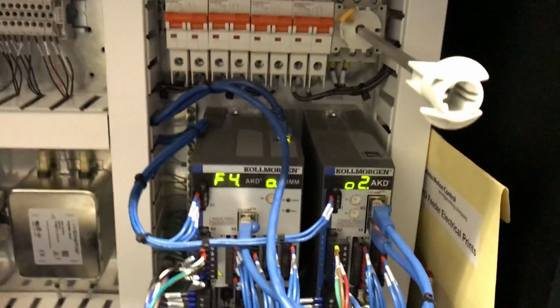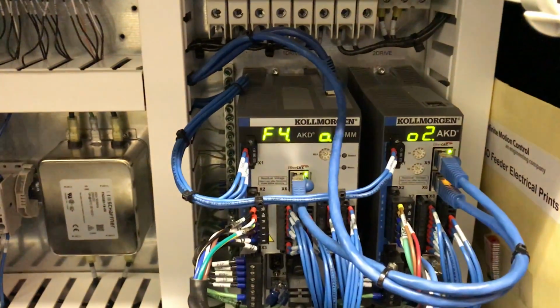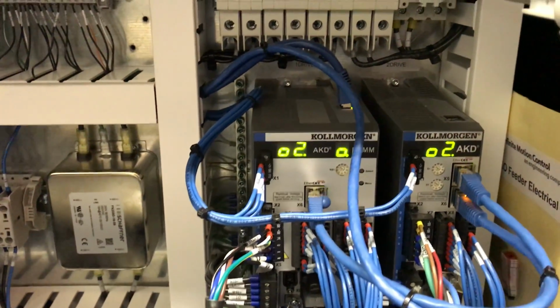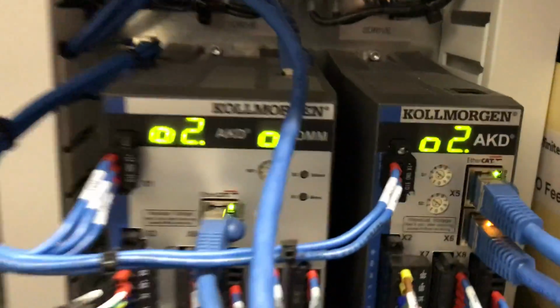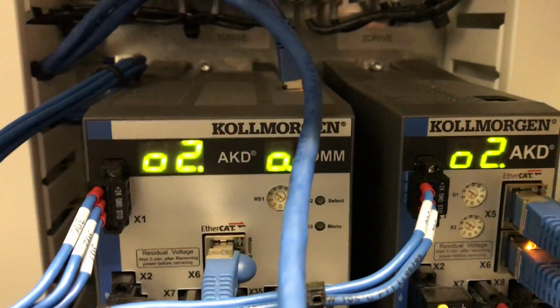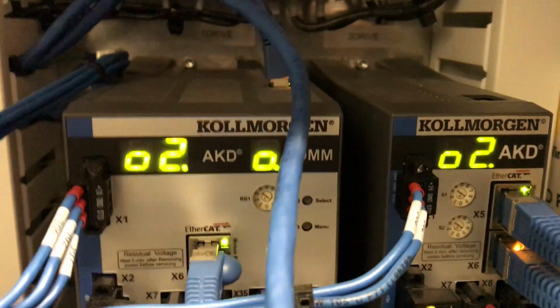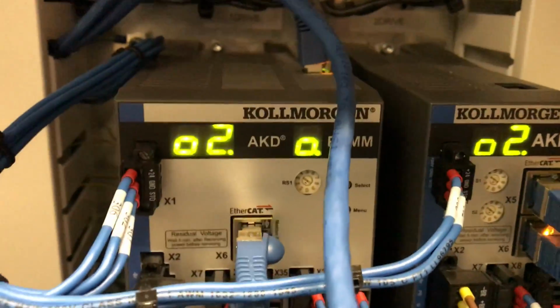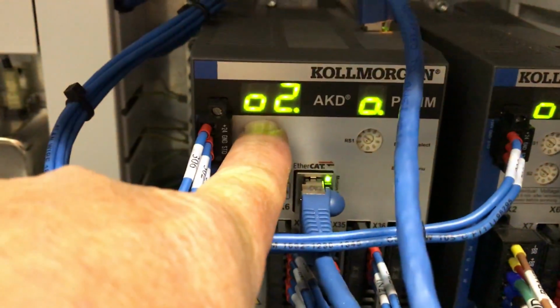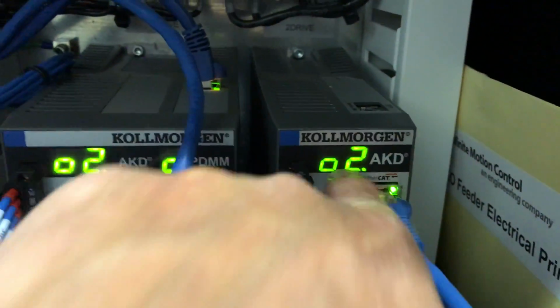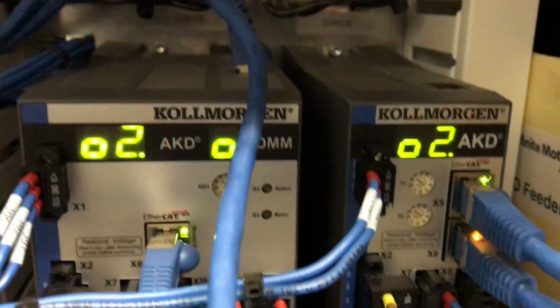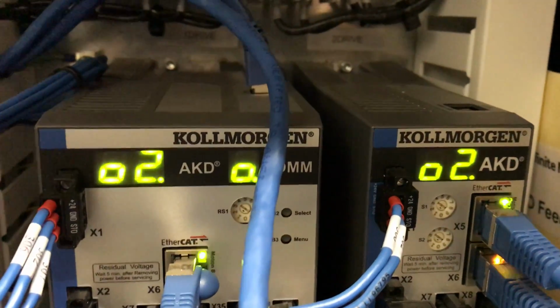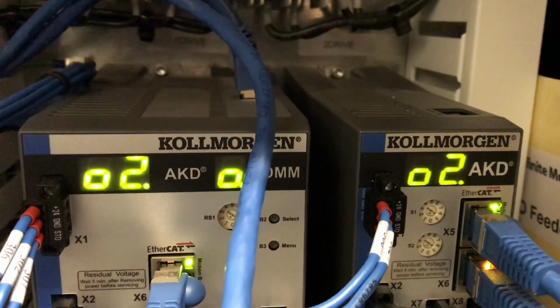So now I'm going to plug this back in, and I'm going to reset the fault. Okay, it's reset. So now O2, once again, that means everything is healthy on this drive. If you went to the HMI, it would say that it's ready. So these are the fault code windows, right there and right there. If it's a non-E-stop fault, you'll see that fault code on the HMI, the touchscreen.